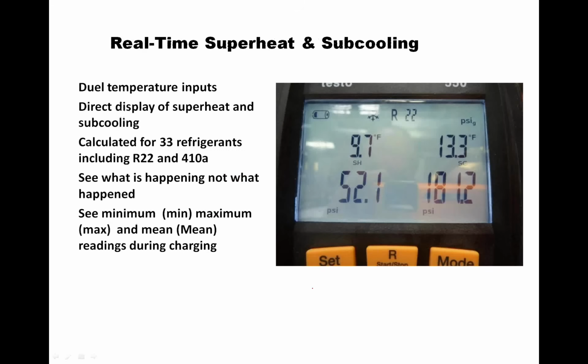The nice thing, again, when you go back to a digital gauge, one of the things I like to point out here, we got superheat, we got subcooling right on the graph. You can see it's 9.7 degrees of superheat, 13.3 degrees of subcooling. The digital gauges, because they're digital, can be very precise in their readings, right? Because now it's not interpolating the temperature pressure chart within 5-pound increments. It's calculating it right down to the 1/10 of a psi and the 1/10 of a degree, so we can get a very accurate reading. We can see what's happening and not what happened. Because we're watching superheat and subcooling at the same time, I can see exactly how both sides of the system are operating. And I can tell if there's problems with the system.